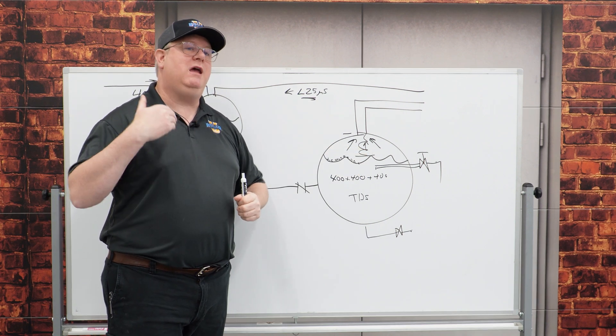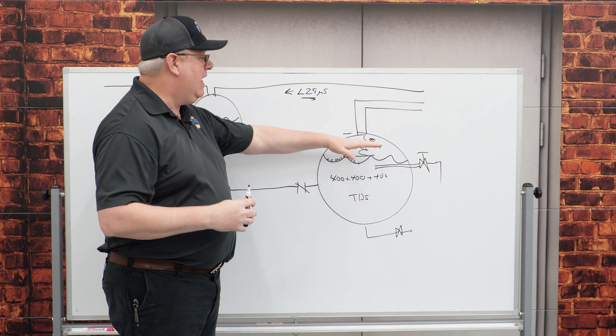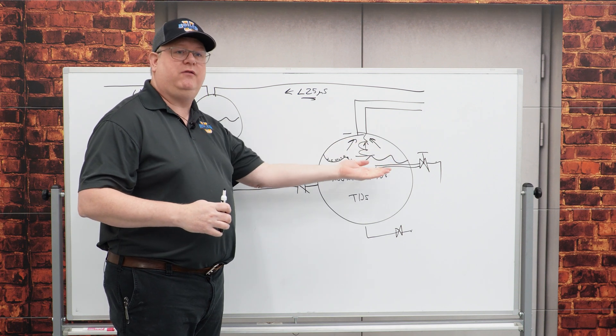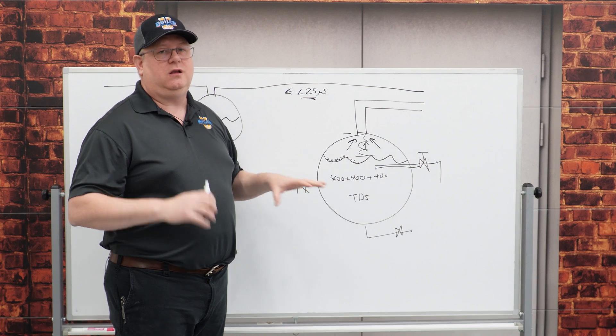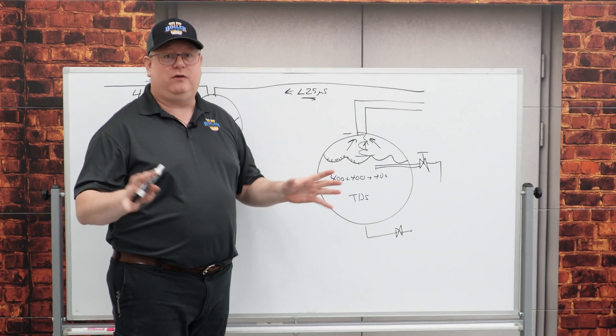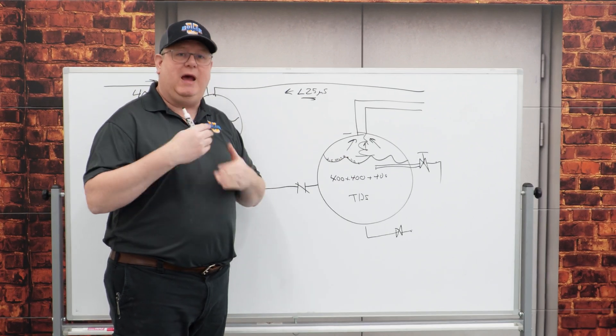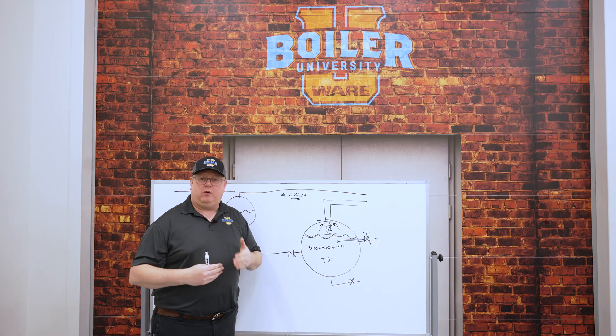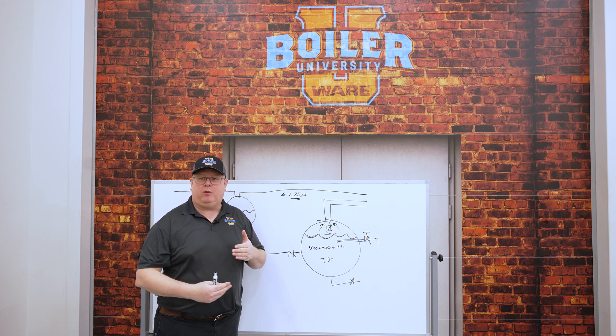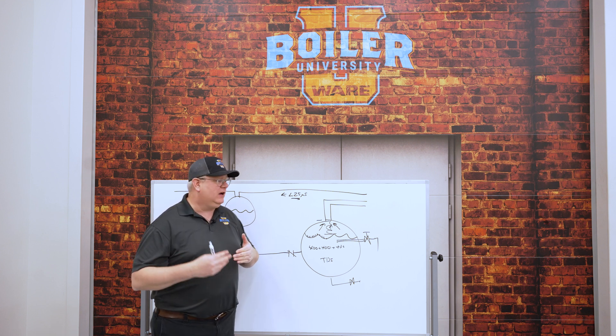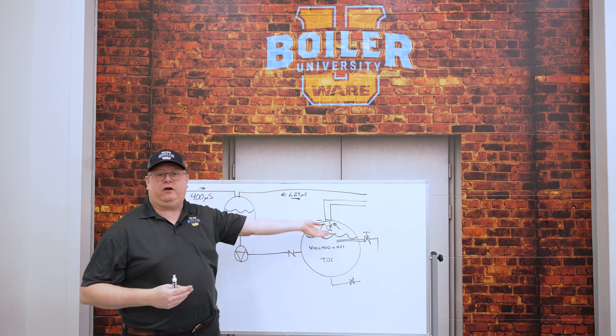Carryover may be intermittent, because at low loads we have lower steam velocity leaving the boiler, so carryover is less likely. But when we have peak demand, we're running the boiler hard, or we're dropping the pressure on the boiler because of system demands, we're more likely to have carryover.